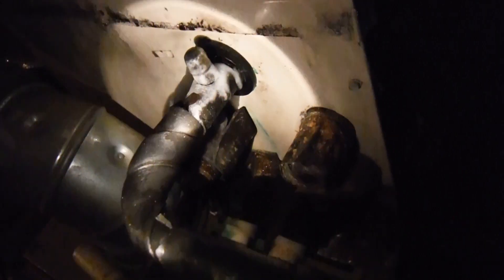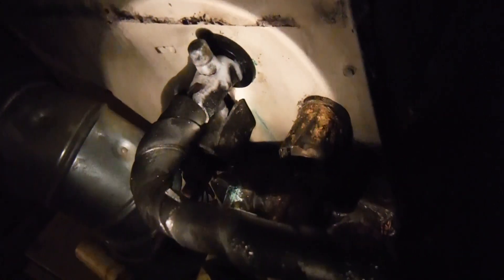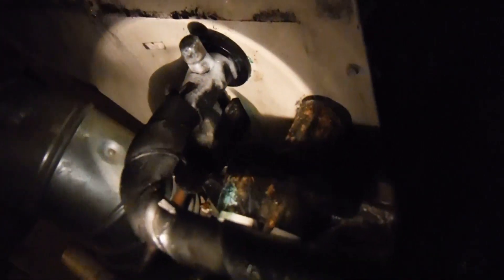Obviously it's causing corrosion there. Usually when it's icing up like this and it's not performing a good cooling differential, this is a culprit right there. It's icing up. It's low on freon. I suspect it has a leak somewhere. I'm going to have to have a licensed HVAC person come take a look at it.